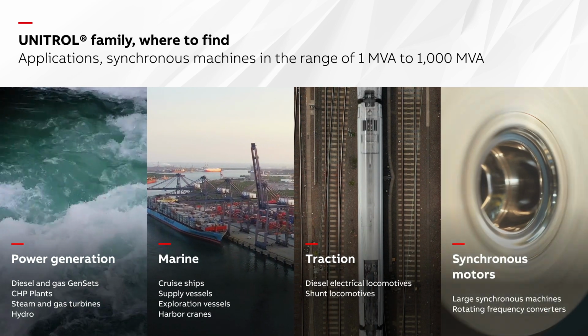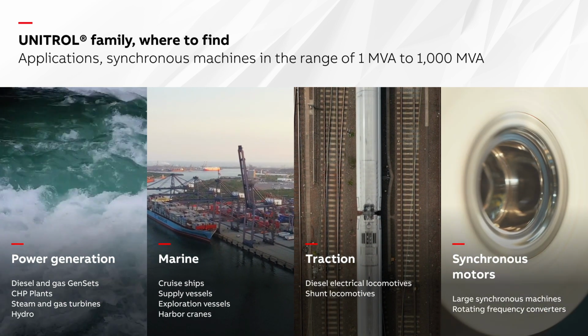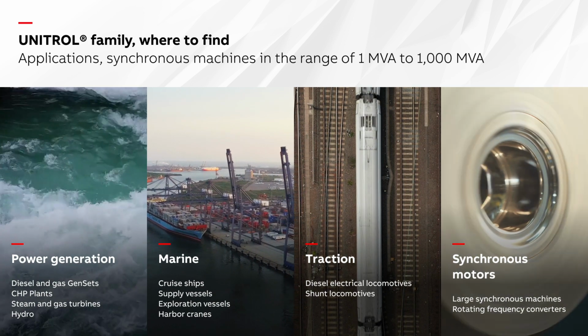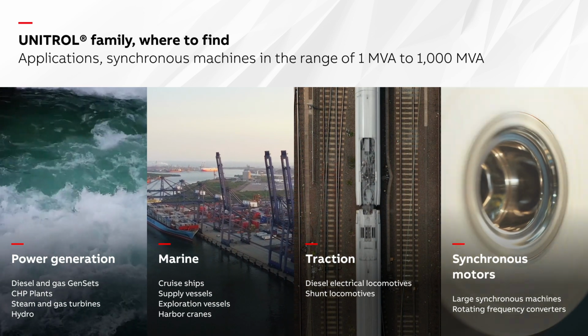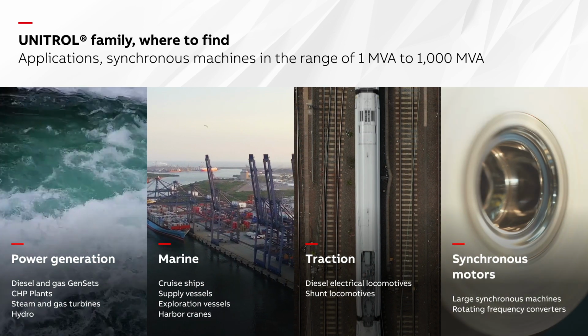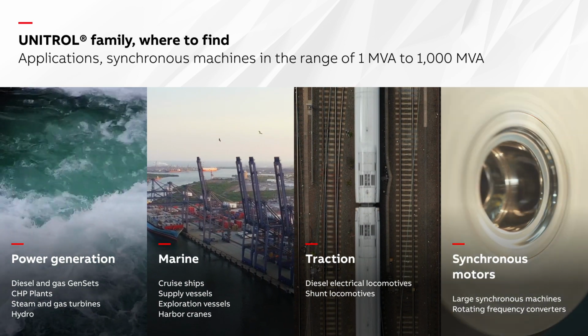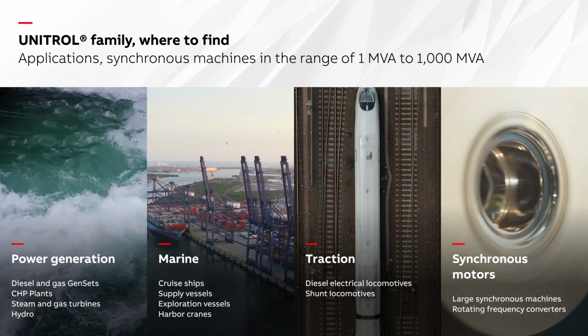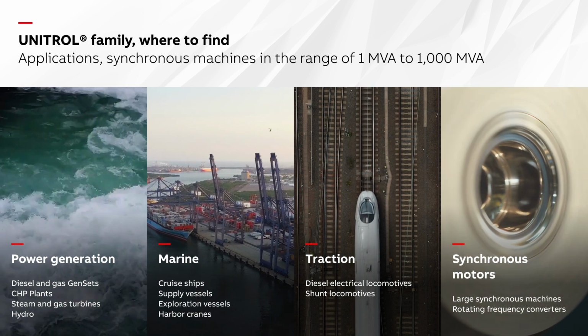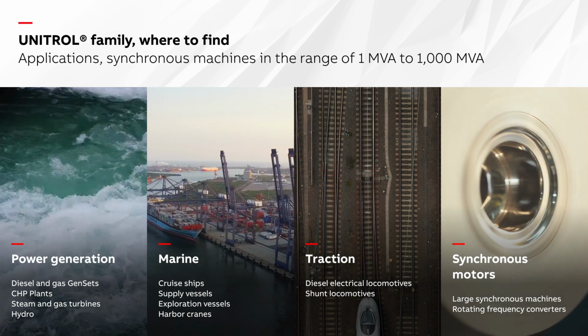The size of the machine can also vary quite a bit. ABB's portfolio expands from 1 megawatt to 1000 megawatts. On the 1 megawatt side, it will be more Unitrol 1000, and on the bigger machines up to 1000 megawatts, you'll find more Unitrol 6000.